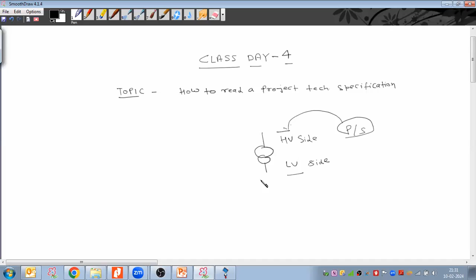Instead of saying primary and secondary, we should say HV and LV side, because if I feed power from one direction, that becomes primary and the other secondary, and if I feed power from the other direction, it reverses. So primary and secondary keep changing, but the voltage doesn't change, so the better terms to use are HV side and LV side.